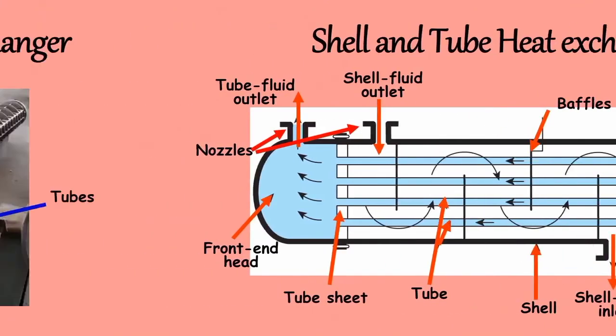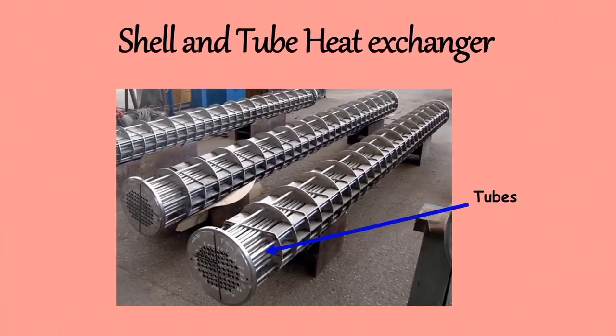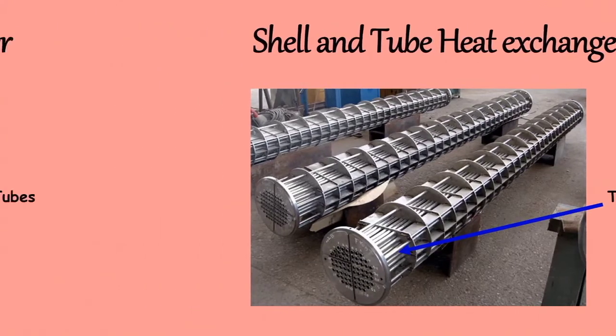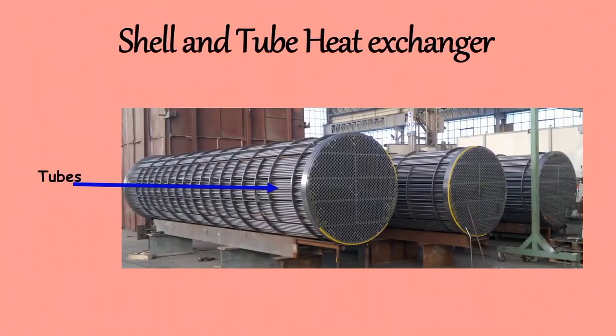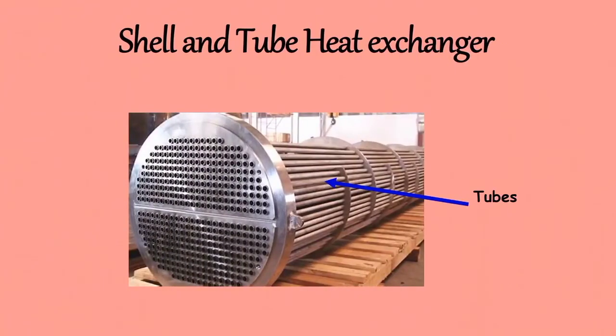The outside diameter of tubes varies from 6 mm to 40 mm. The tubes with outside diameters of 19 mm and 25 mm are very common. The tube lengths used are 0.5, 2.5, 3, 4, 5, and 6 meters. The wall thickness of tubes is usually expressed in terms of Birmingham Wire Gauge (BWG), and it depends upon the material of construction and diameter. For 19 or 25 mm outside diameter tubes of mild steel, 10 or 12 BWG is common.